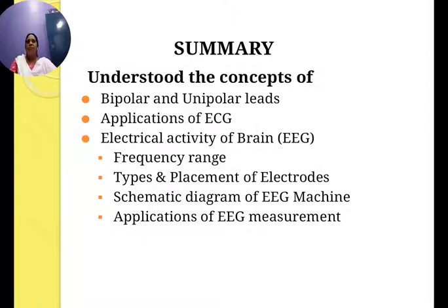The electrodes are identified by their positions on the head by letters: capital FP for frontal polar, capital F for frontal, capital C for central, capital P for parietal, capital T for temporal and capital O for occipital. Odd numbers refer to electrodes on the left side of the head and even numbers represent electrodes on the right side, and Z denotes the midline electrode. One electrode is labeled as ground, and this is placed at a relatively neutral site on the head, usually the midline forehead.